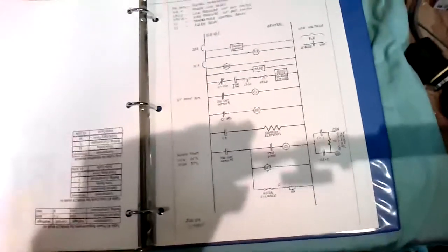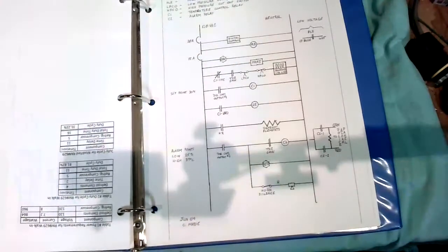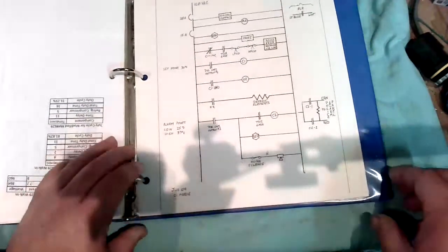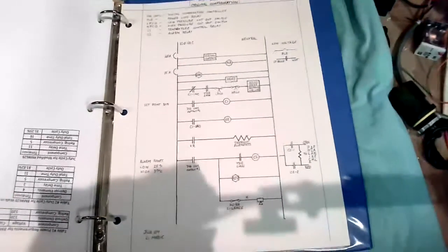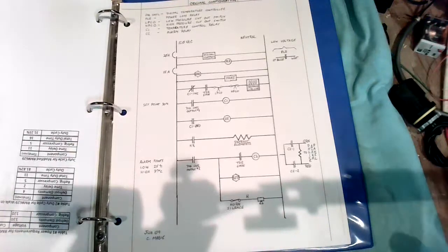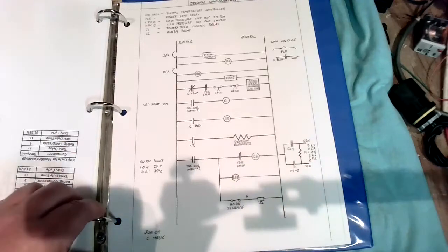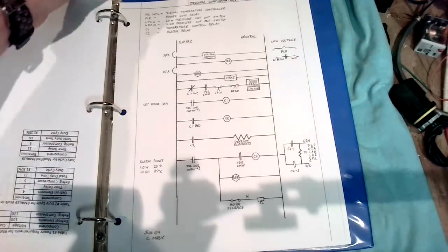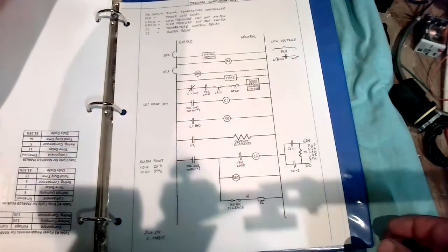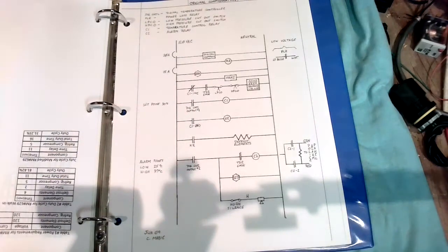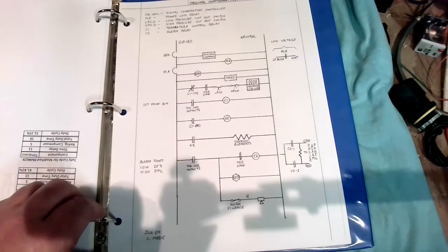So this was a project that I took on. They were having a problem in one of the labs where a chamber, basically a lab area, that they had a lab going on, an experiment going on, and it was short cycling their compressor for the air conditioning for this one place. So I looked at it. Their controls were all hardwired. There was no PLCs or anything with it. Well, a timer, but I wouldn't call it a PLC.